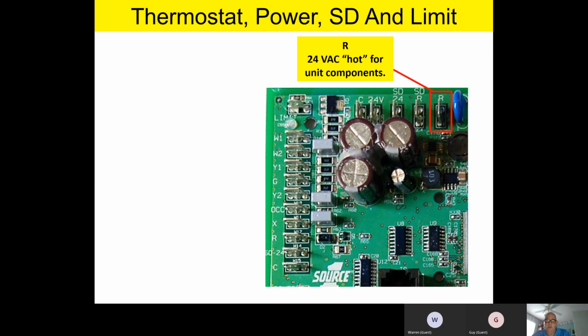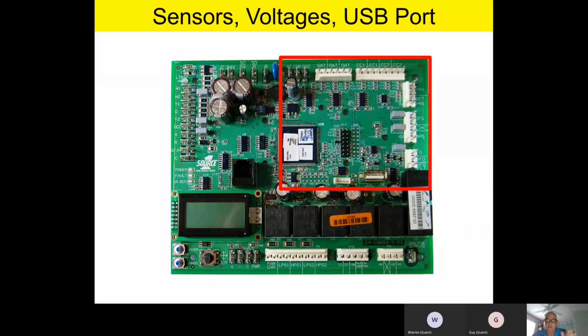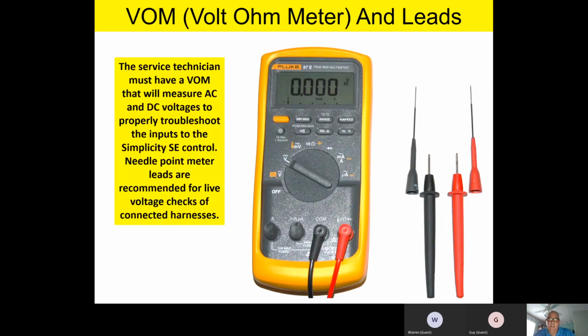Okay, the next area we're going to talk about is sensors and voltages on those sensors, as well as the USB port. Again, looking at the board, we're going to take a hunk of that board, pull it out and blow it up, and then talk about all of those functions. One of the things I like to encourage, especially when you're using and checking sensors, is that a service technician has a good, high quality volt ohm meter.